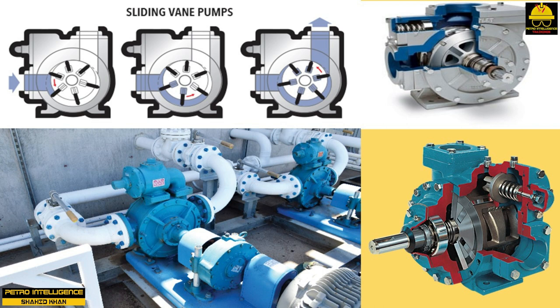The vanes on the pump are made of a softer material than the rotor and casing. A bevel on each vane closely matches the rounded edges of the chamber, and the softer vane material tends to wear evenly during the life of the vane. Sliding vane pumps typically are used with process liquids that have good lubricating qualities. Vane pumps are used in hydraulic systems, vacuum systems, and low-pressure oil systems. The typical vane pump has a capacity of 380 GPM and operates with a pressure differential of 50 PSIG.